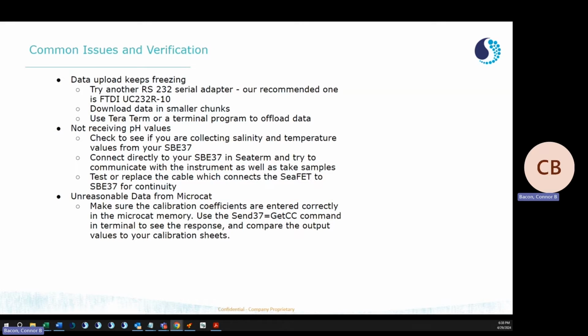Next, if you're not receiving pH values, check to see if you're collecting salinity and temperature values from your 37. Without it, the pH values will not be generated. The best way to do this is to connect directly with your MicroCAT in Seaterm and try to communicate with the instrument as well as take samples. If all else fails, test or replace the cable which connects the SeaFET to the 37 for continuity.